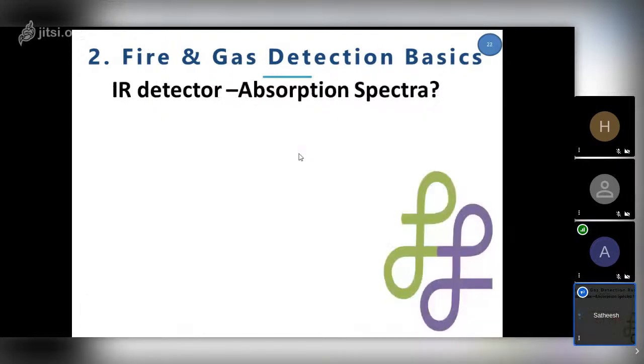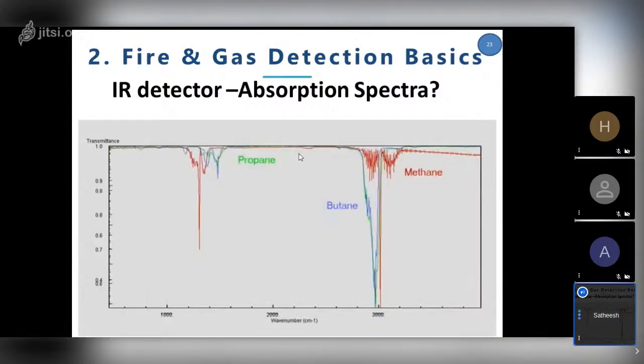Now, the next one, this is the most attractive gas detector: the infrared gas detector. IR stands for infrared. Infrared gas detectors are the number one application for flammable gas detection. Here we call it absorption spectra. We'll not go into very much detail. What we're trying to understand here is any hydrocarbon gas. Here we will be careful: not hydrogen, but hydrocarbon, HC, hydrocarbon molecules. When they see the infrared beam, infrared is one source of light at a specific wavelength in the spectra. Like UV, ultraviolet, is another one.